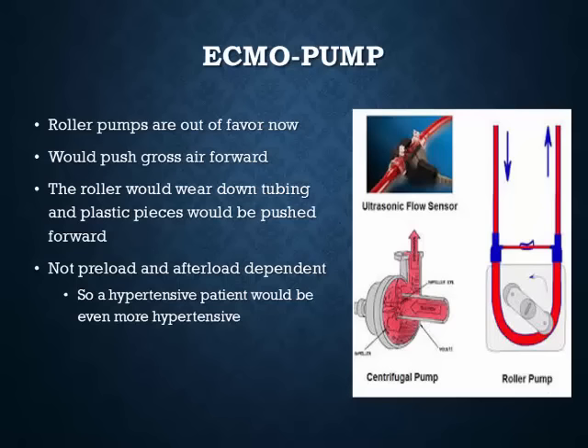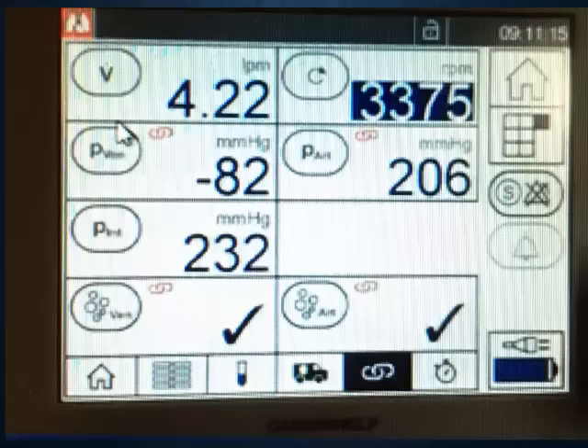Roller pumps are also not preload or afterload dependent. So if your patient was getting better and becoming more hypertensive, they would become even more hypertensive. If you weren't watching the pump closely while watching the patient, you wouldn't understand what was happening with the blood pressure — you could easily overshoot.